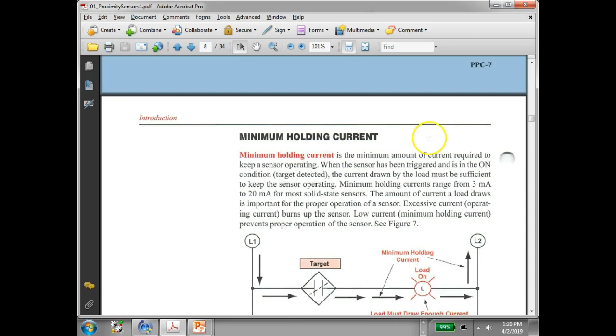And then the holding current is how much current the load has to draw to keep this thing turned on, right? Makes sense? Solid state devices have what we call the holding current. Once you turn that solid state device on, if you drop below the holding current, it's going to cut off. That means we have to have a load out there that pulls current. If my load didn't pull enough current, we'd use our solid state relay to pull in a control relay, and then we'd use the control contacts to run that very low current line. Does that make sense?